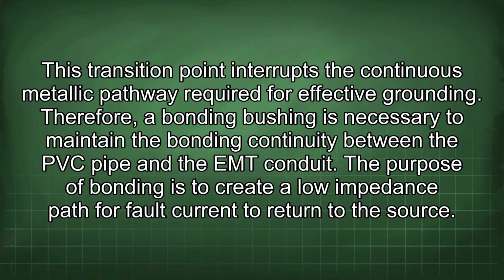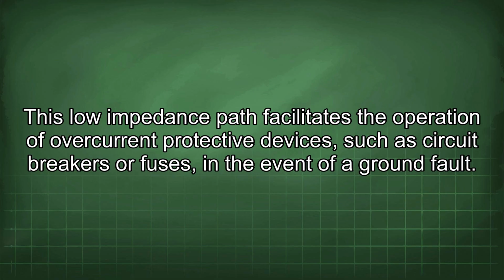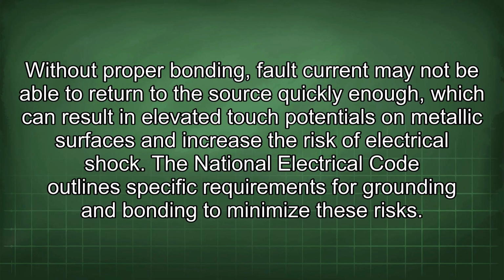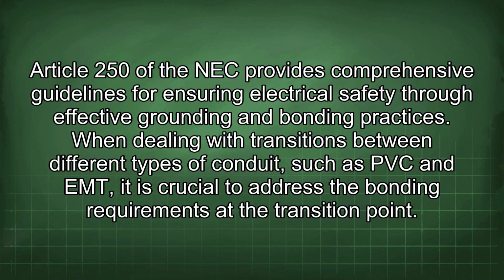The purpose of bonding is to create a low impedance path for fault current to return to the source. This low impedance path facilitates the operation of overcurrent protective devices such as circuit breakers or fuses in the event of a ground fault. Without proper bonding, fault current may not be able to return to the source quickly enough, which can result in elevated touch potentials on metallic surfaces and increase the risk of electrical shock. The National Electrical Code outlines specific requirements for grounding and bonding to minimize these risks. Article 250 of the NEC provides comprehensive guidelines for ensuring electrical safety through effective grounding and bonding practices.